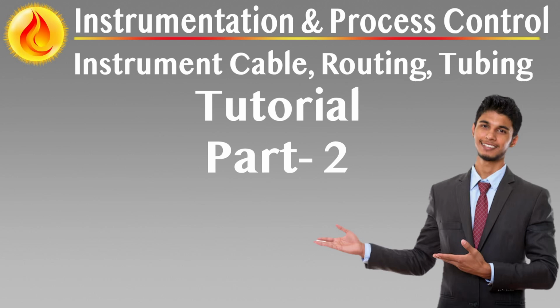Installation best practices for pneumatic systems. All pneumatic fittings must be of the compression type and compatible with the tubing diameter and material. Brass and engineered plastics are acceptable, subject to pressure and temperature ratings. Fittings shall be selected based on reliability under vibration and thermal cycling, especially in outdoor or high-traffic areas. Where tubing exits trunking systems, bulkhead unions must be installed to preserve enclosure integrity and prevent tubing strain.